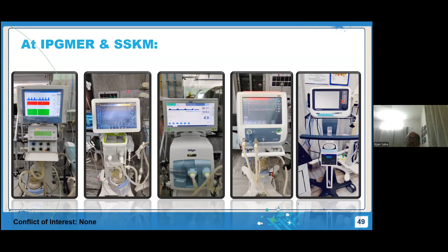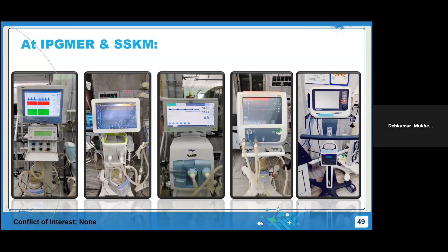So what we have to do, if you use Babylog 8000 plus or a Dräger machine, where there is no automatic flow adjustment, is manually adjust the flow based on the pressure you have set, seen in the graphic. So how do you know that your flow is adequate? In the graphic, you will see whatever pressure you have set, the same pressure is delivered by the machine. That means your flow is adequate.